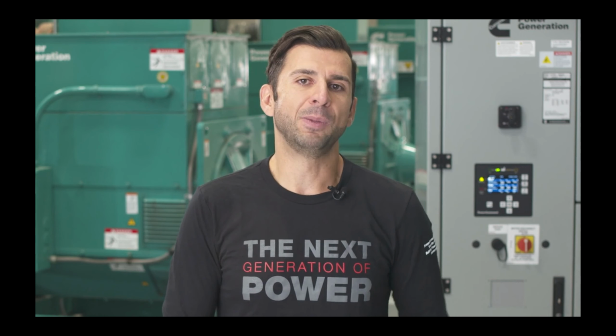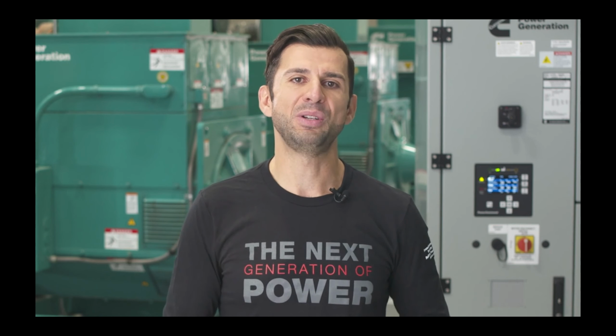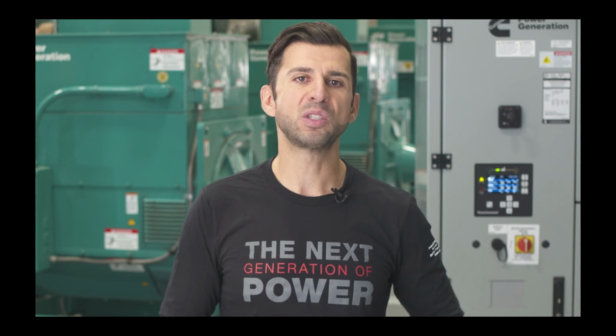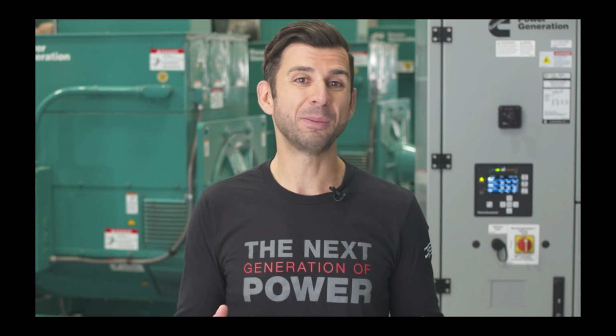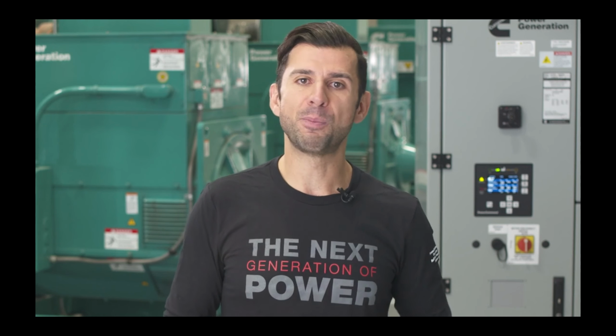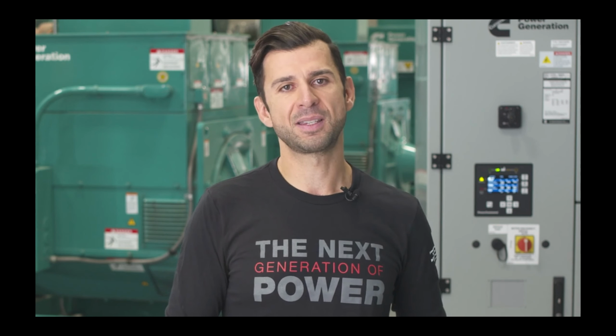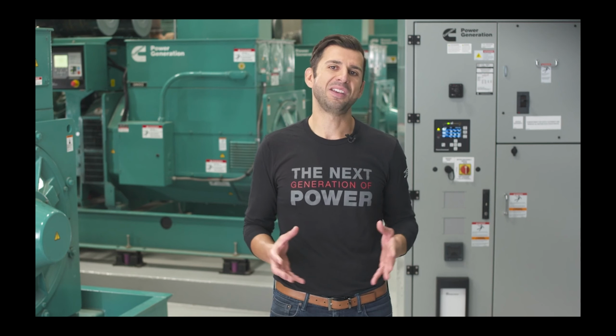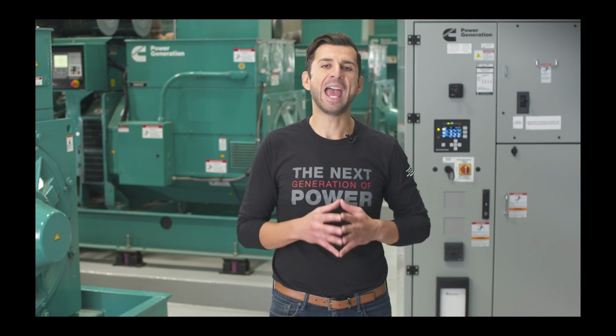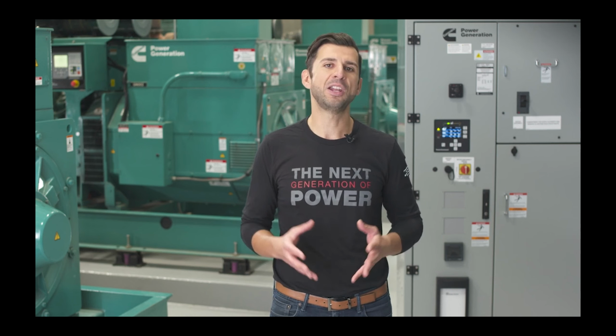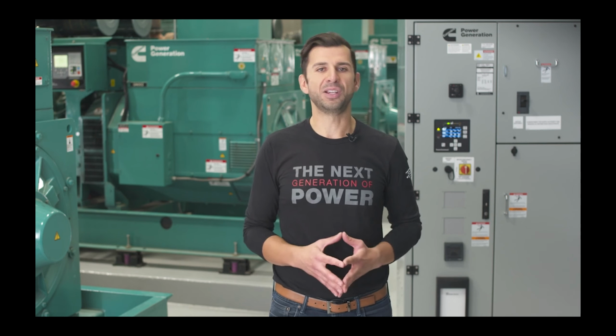Because of our patented blow-on design, Cummins X series transfer switches have the highest withstand and closing rating, or WCR, in the industry for both time-based and short-time ratings. These short-circuit WCR values have been tested and verified to meet UL 1008, the toughest standard in the industry. The high WCR capability in both magnitude and duration allows for high survivability in extreme fault conditions that often blow out or damage other switches.